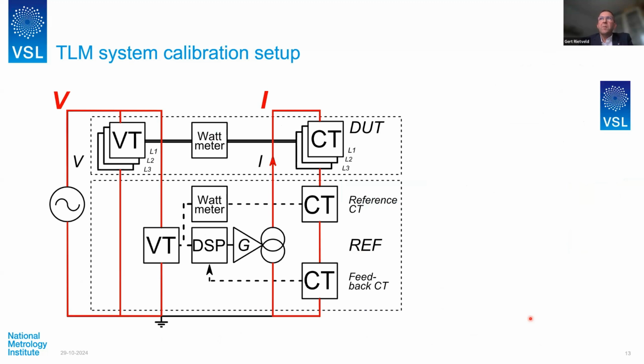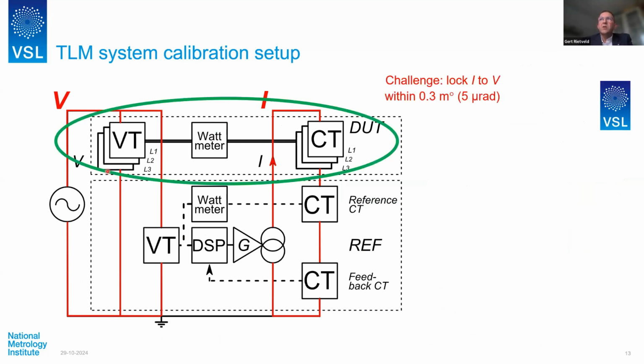So this is the schematic. At the top end, you see the system of the power transformer manufacturer. So there are 3 channels. It's a 3-phase measurement. And what you do is you put all voltage channels in parallel and you apply a voltage. And then you put all current channels in series and you apply a current with adjustable phase through all 3 CTs in series. And then the challenge in the calibration is to simulate this power transformer with adjustable losses.